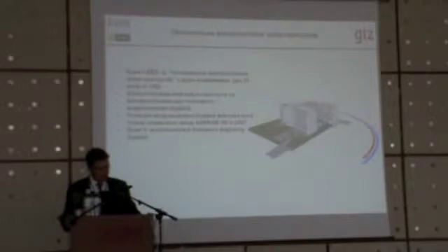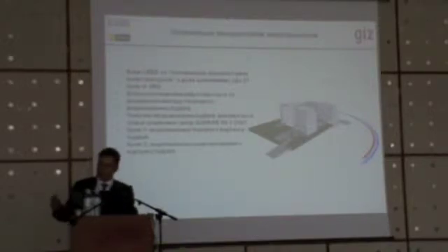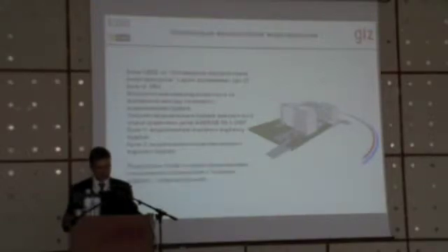So the basic idea is to simulate a baseline building with defined U values, efficiencies and HVAC systems by the ASHRAE. But you have to use the architecture of your building, and in the second step you have to simulate the building as it is planned. So you are using the U values and the shading systems which are really planned for the proposed building. And finally you have to calculate the difference to analyze the energy savings between the baseline building and the proposed building, and according to these energy savings you earn points.